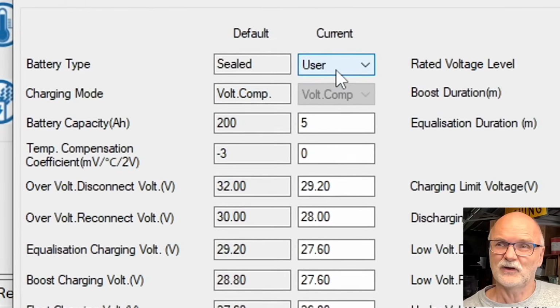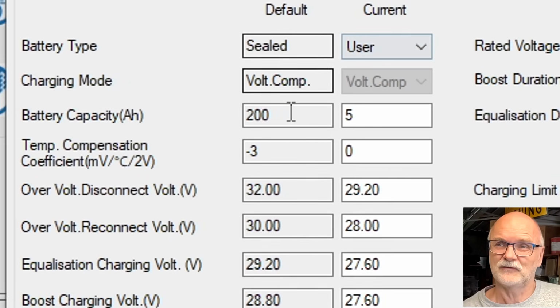I've set this all up as good as I could, using the user profile basically. This is the default: 5 ampere hours capacity, overcharge disconnect at 29.2 volts, which is 3.65 per cell. Reconnect, equalization, we usually don't use with lithium products.